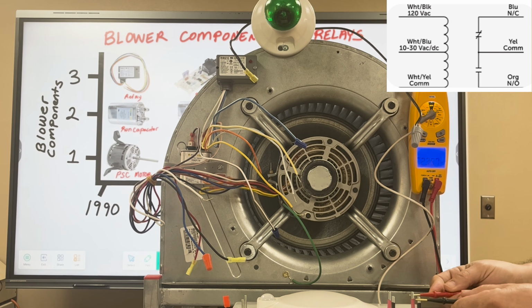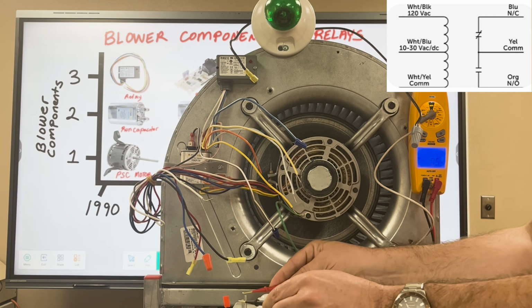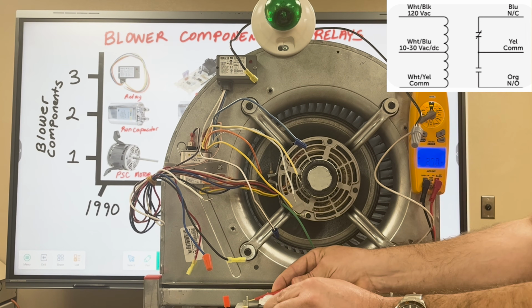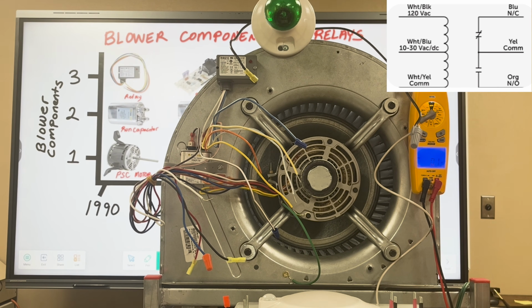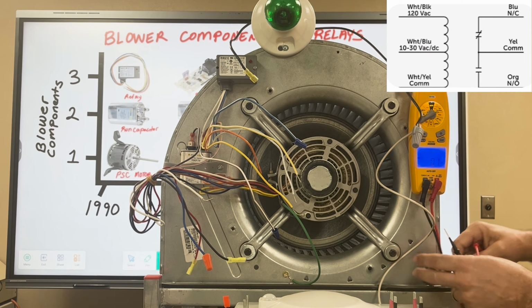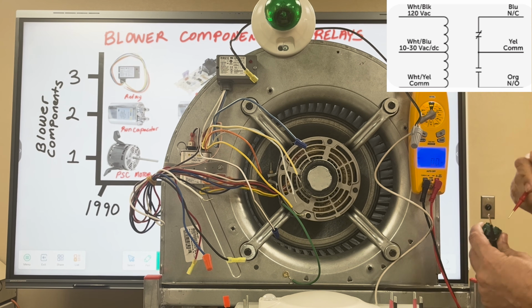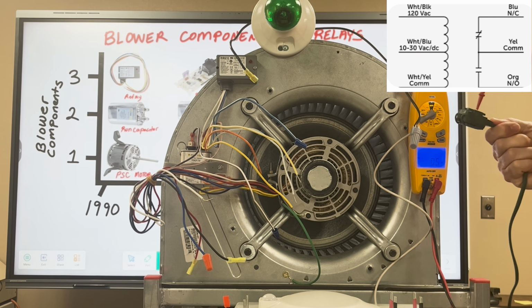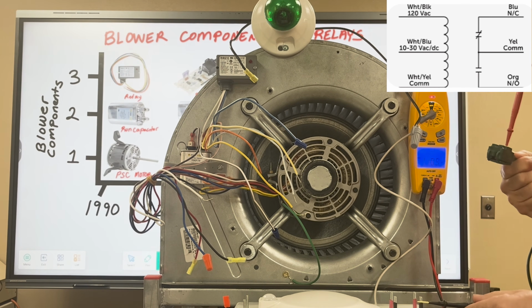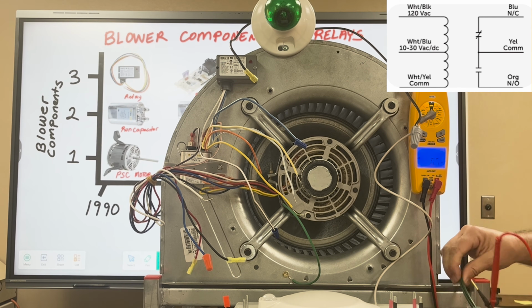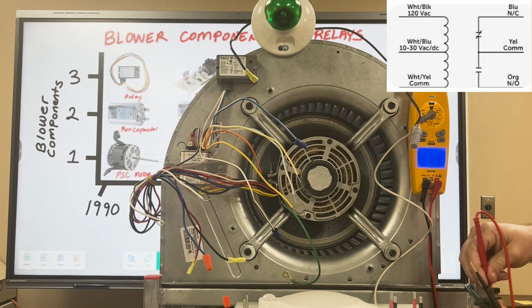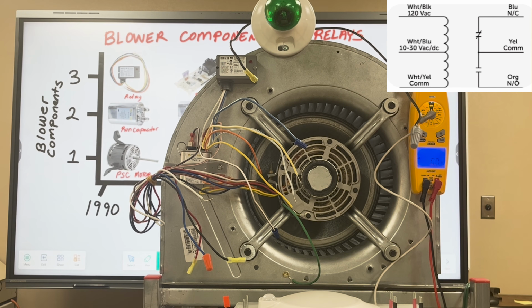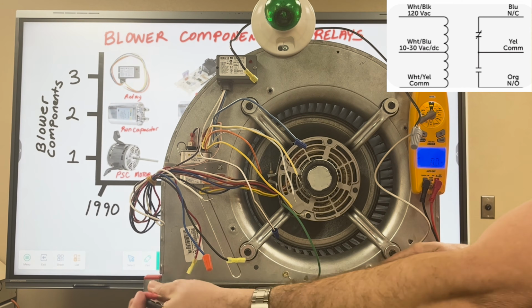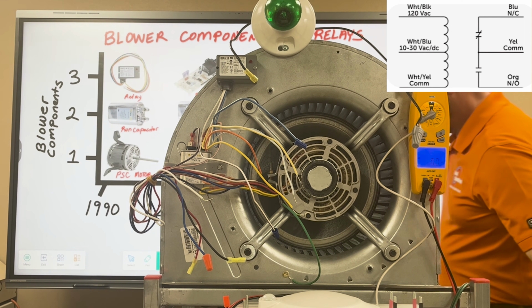When I come over here to line voltage, you'll read 239, we'll call it 240 volts. And when I come over here to R and C, you should see that we have 27 volts. With that, I have an extension cord here, a little green extension cord. I'm going to show you where I have 120. If I put one lead inside the extension cord for neutral and go to any one of these, you'll see that I have 120 per leg. I'll need that if I want that light to come on. And so we're going to go ahead and show you now how to wire this up to the light by itself.